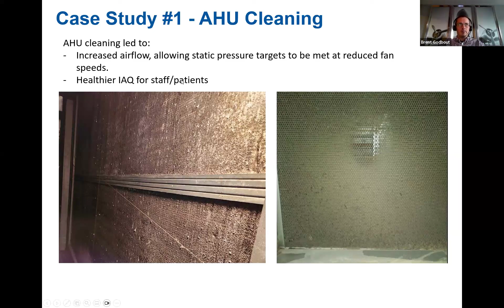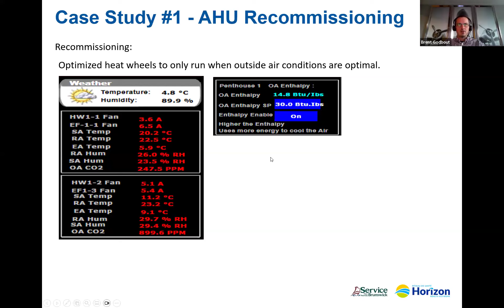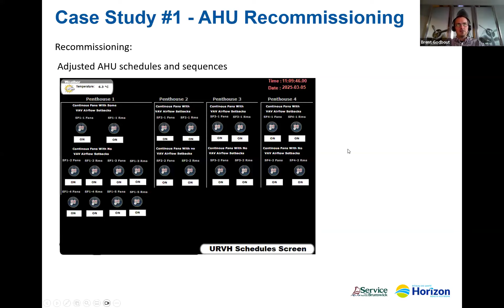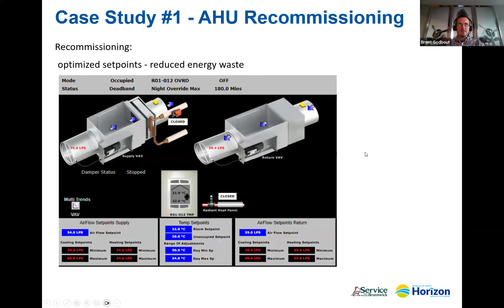We also, because of this work, were able to do a bit of a mini recommissioning at the same time. Wasn't a full-blown commissioning like we had done back in 2018-19, but we definitely were able to optimize our heat wheels to make sure they're running at optimal conditions based off enthalpy. I'm not going to get into these too much, but we adjusted the air handling unit sequences and schedules. Also optimized some set points to reduce waste energy.